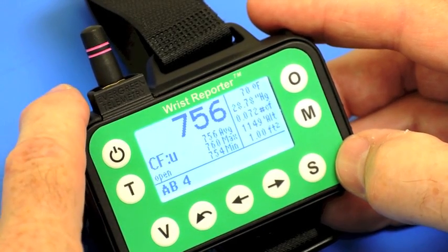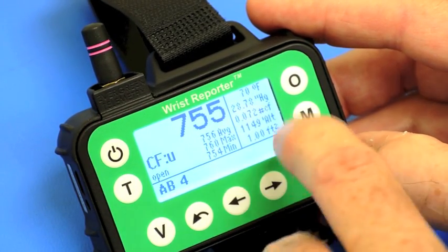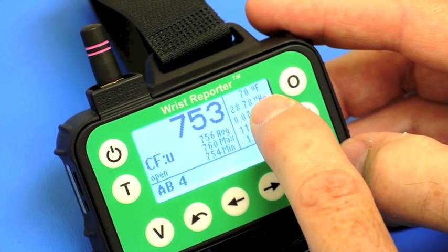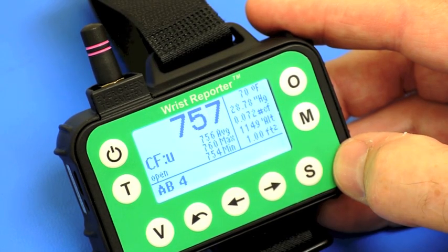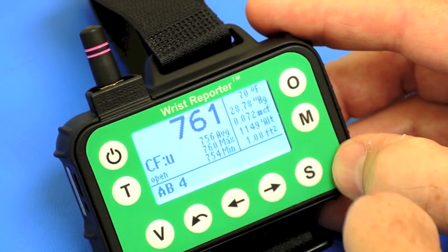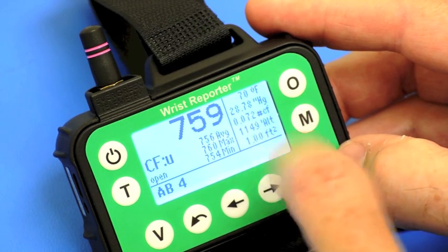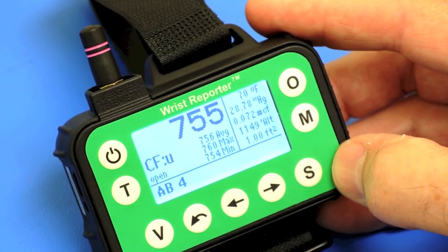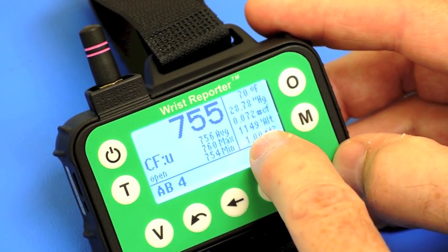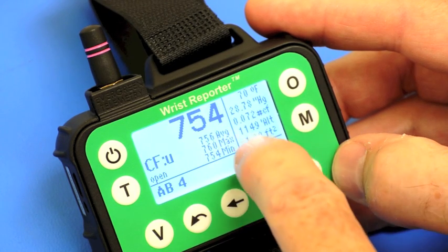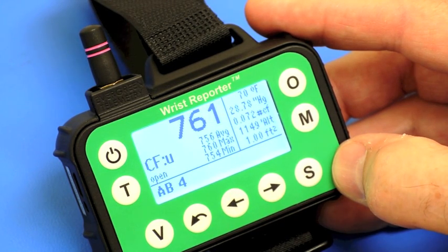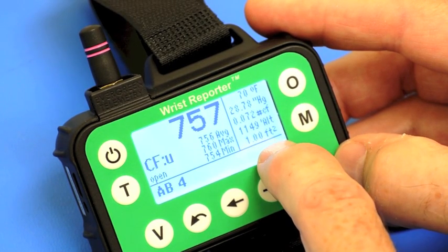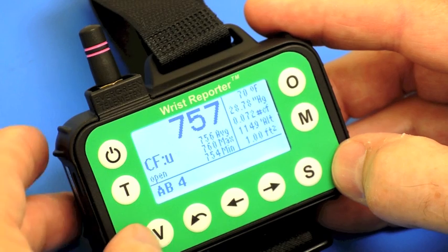What this view brings is shown at the upper right — these are my assumptions on the density of the air. We're operating in a standard 70 degree F mode. The pressure module automatically measures the barometric pressure at 28.78, giving a density of 0.072 pounds per cubic foot. The calculated altitude shows 1149 feet of elevation, and we've designated a cross-sectional area here as well.